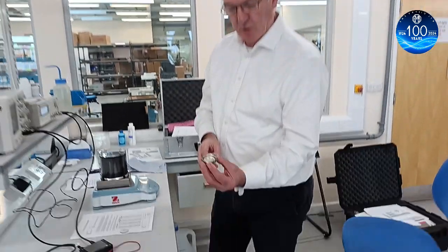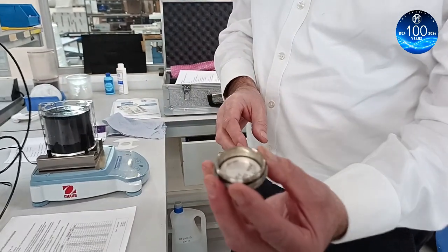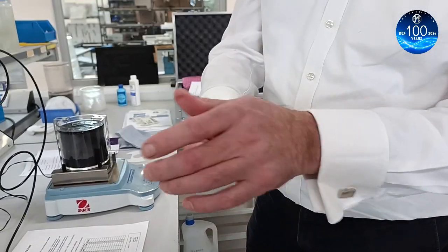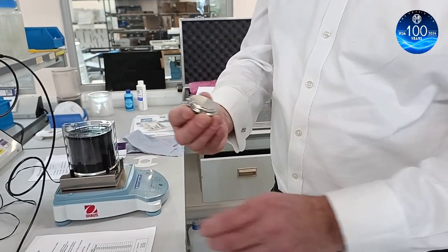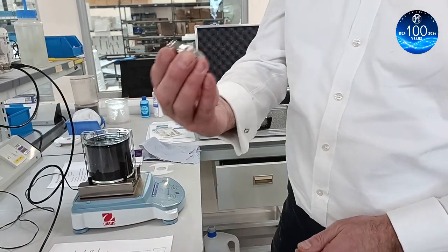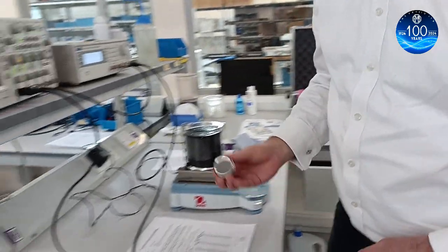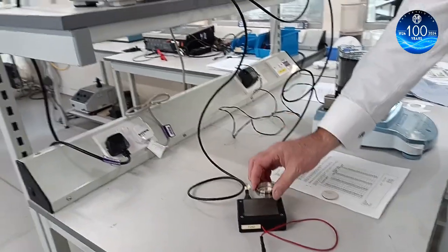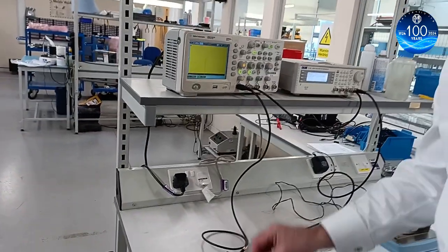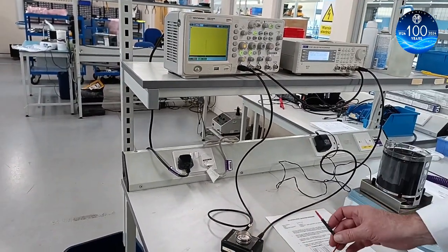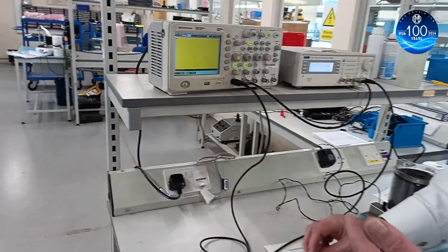The crystal is now bonded into the steel, cured in the oven, and the front face of the steel is polished. This is actually not a brand new steel, but it's just been used for the purpose of this video. What we now do is check that the crystal is still responding correctly now that it's bonded to the steel.